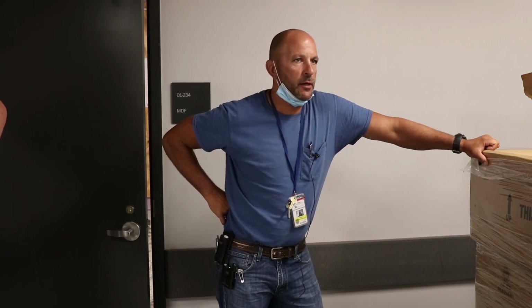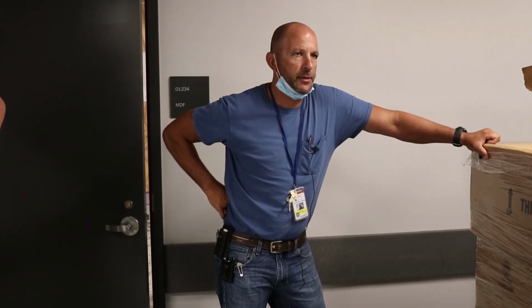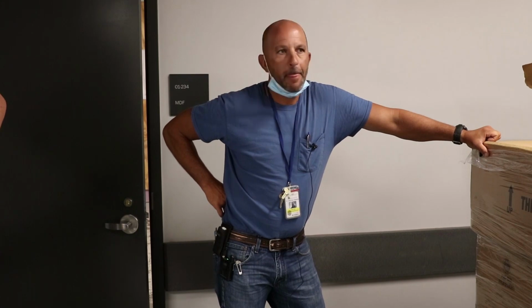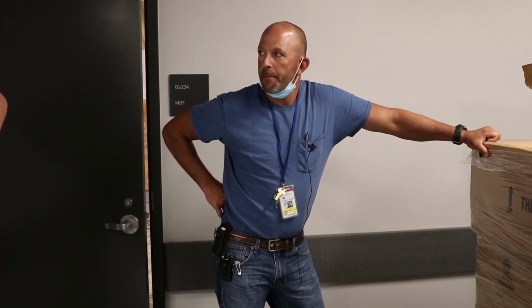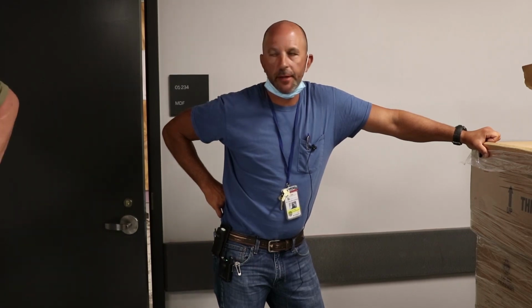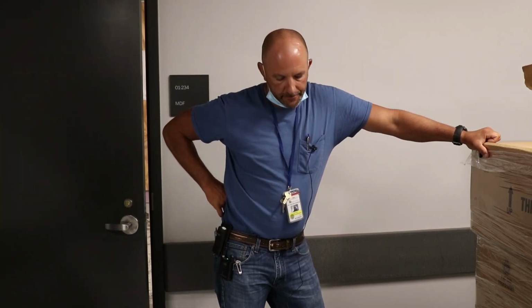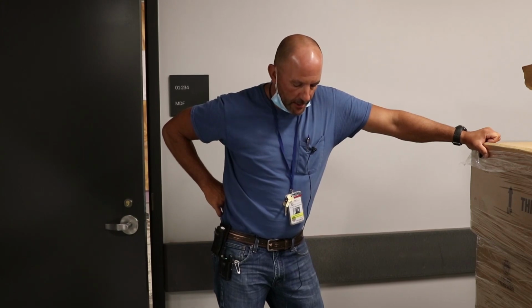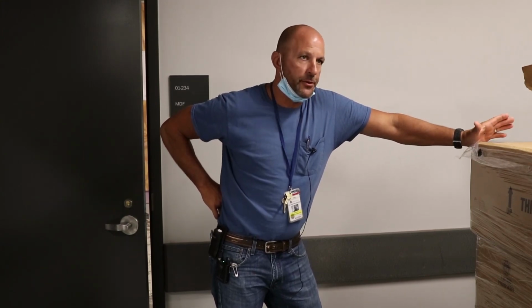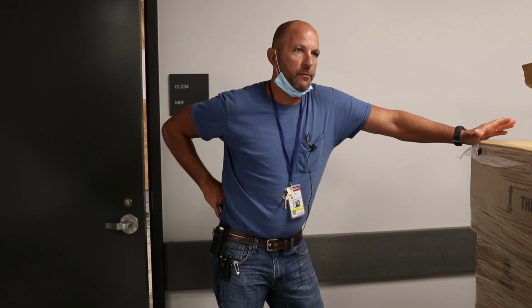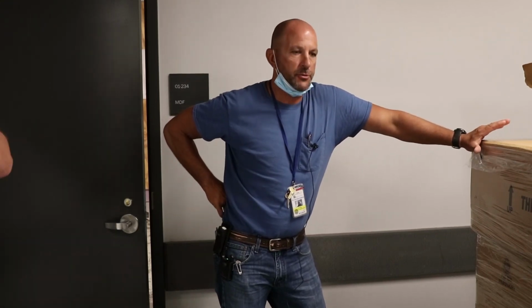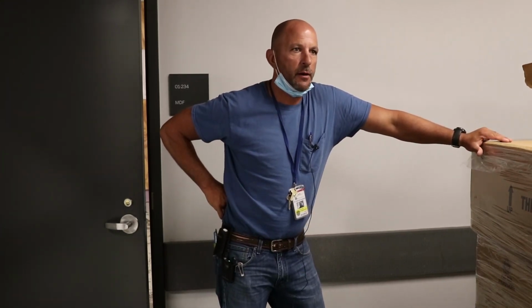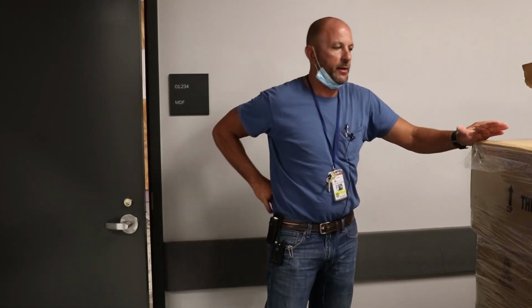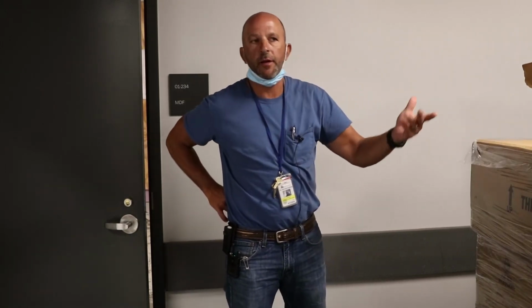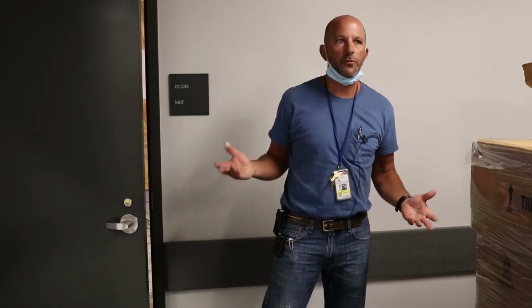Do you exercise the dampers in the other building? No, the safety department handles that. The company that does it is Simplex, part of Tyco. A lot of times, like in schools, they'll set the alarms off but it doesn't put anything into alarm, so they're not actually tripping dampers. There are probably mandates like FDNY requirements to exercise them periodically, maybe every 3 months or so.